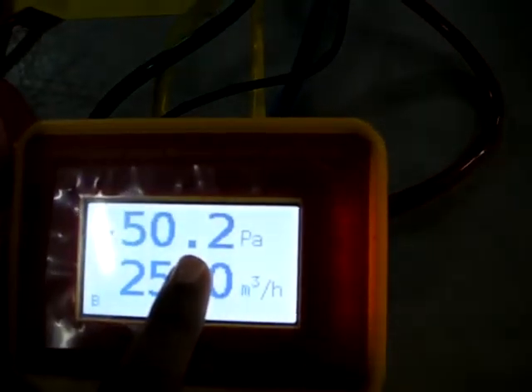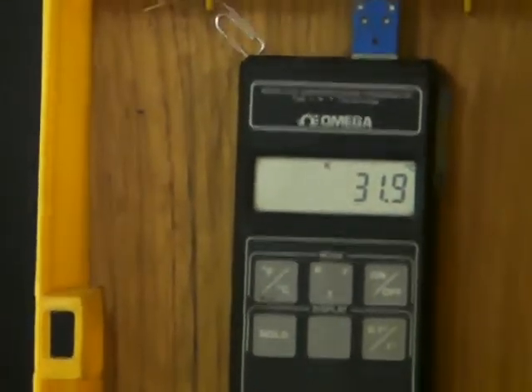First of all, we record the ambient condition, 33.3 degrees, relative humidity of 24%, ambient pressure of 1013 MB. We record a conical inlet of 60, in chamber pressure of 50.2, and an airflow of 2520 with a fan pressure of 72.2. And next we record from the digital thermometer the temperature inside the chamber.